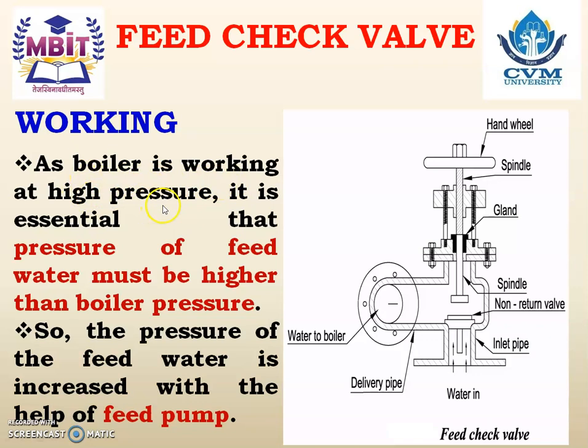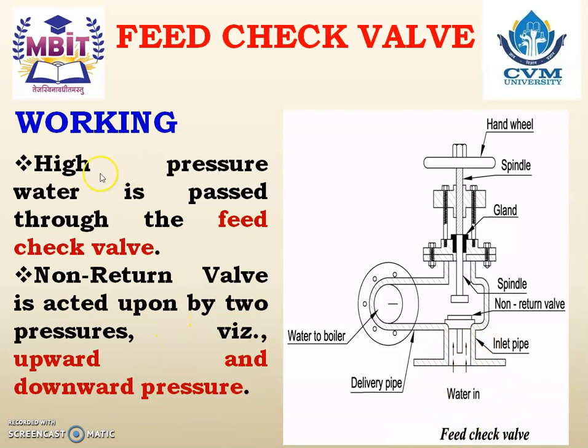As the boiler works at high pressure, it is essential that the pressure of feed water must be higher than the boiler pressure. If it is not, water will not enter the boiler and there can be a reverse flow — water from the boiler can come out. So the pressure of feed water is increased with the help of the feed pump. Initially water enters the feed pump where pressure is increased, and high pressure water is then fed into the feed check valve.